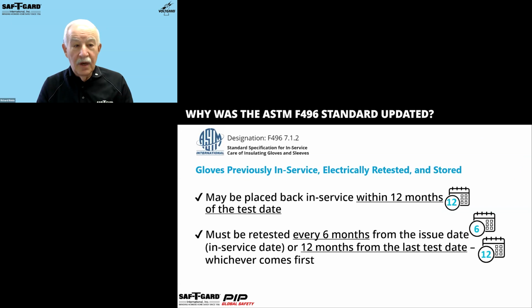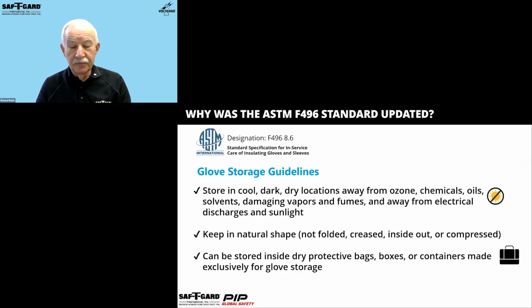This is clear. Now, gloves that were previously in service within 12 months can be stored as required safely and put back into service, but in no case can they be used beyond 12 months from that test date. This is the 2024 update to the ASTM standard.